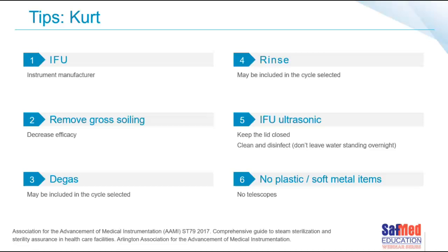The following one is removing gross soils. Although certain brands and models, which we'll discuss later, have a pre-wash, you need to pre-rinse prior to putting instruments into an ultrasonic bath. It's to make sure we're getting the optimal efficacy of cleaning, because that debris will end up lying inside your ultrasonic bath, and then you can cross-contaminate other instruments. So removing gross soils is very, very important.